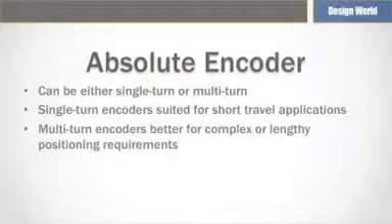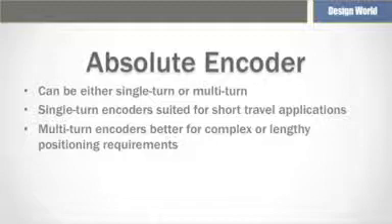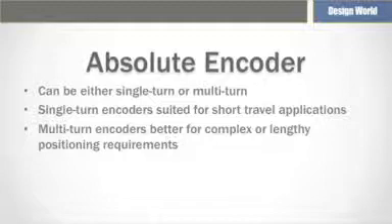Absolute encoders can be either single-turn or multi-turn. Single-turn encoders are well-suited to short-travel motion control applications where position verification is needed within a single turn of the encoder shaft. Multi-turn encoders, on the other hand, are better for applications that involve complex or lengthy positioning requirements.